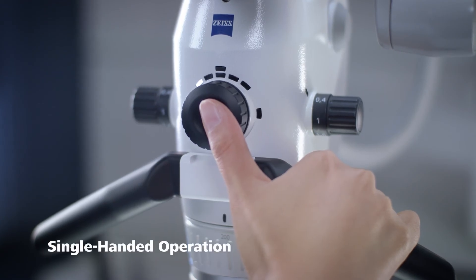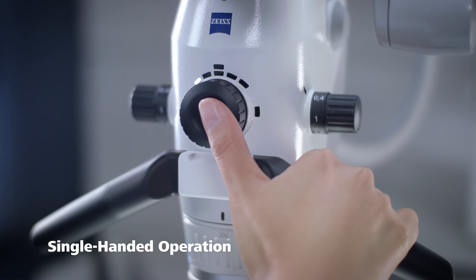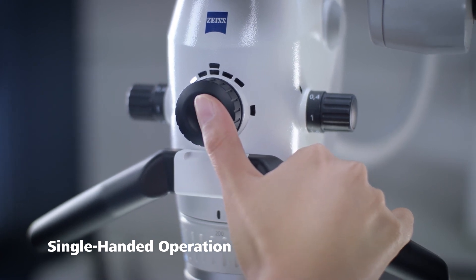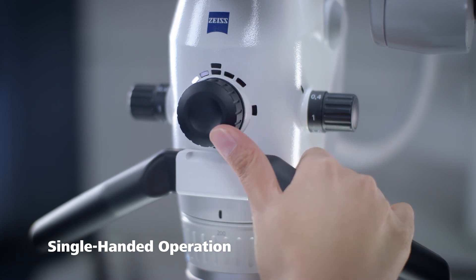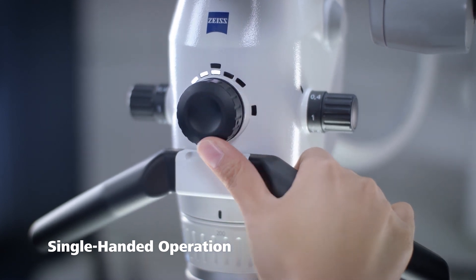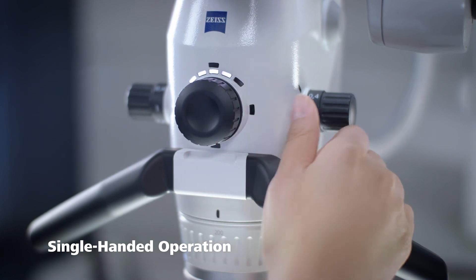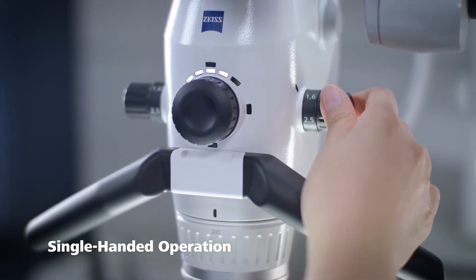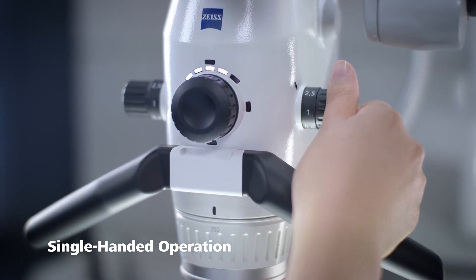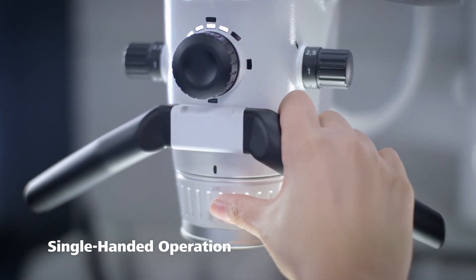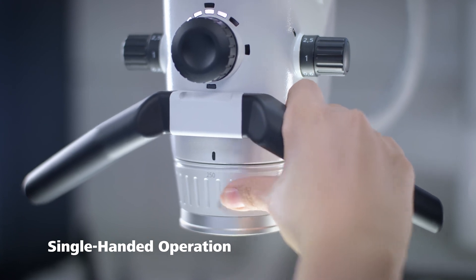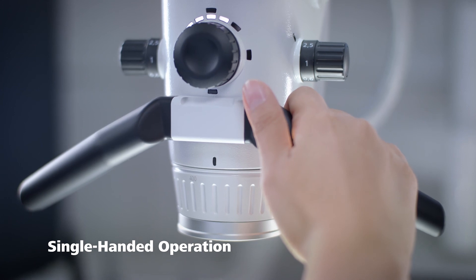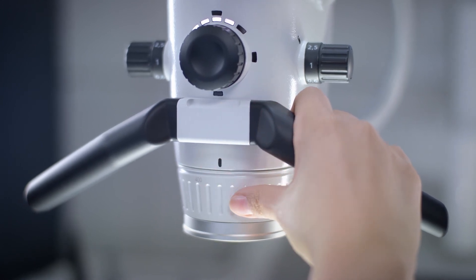The microscope body of the Zeiss Extaro 300 is designed in a way that you can reach the multi-functional mode control to activate all visualization and capture modes as well as the light settings with only one finger. From the same hand position you can adjust the magnification, change the working distance of between 200 and 430 mm with the varioscope 230. This enables an uninterrupted workflow during treatment in all situations.